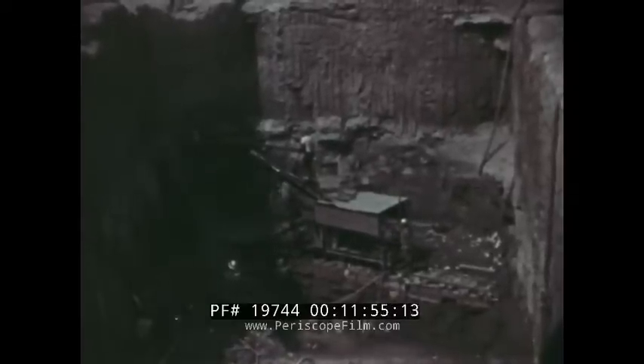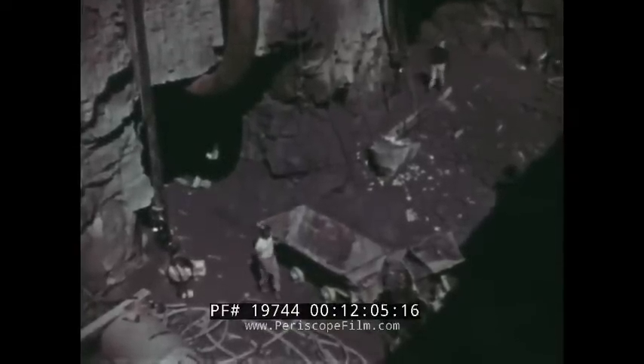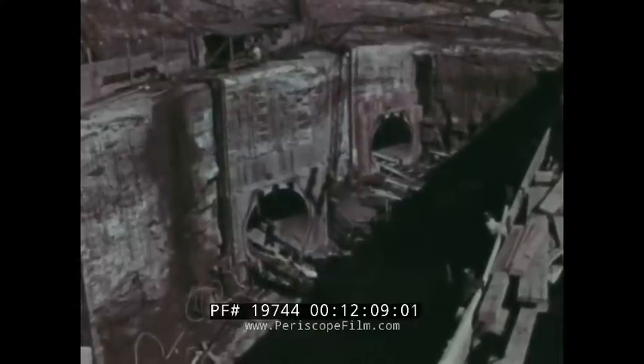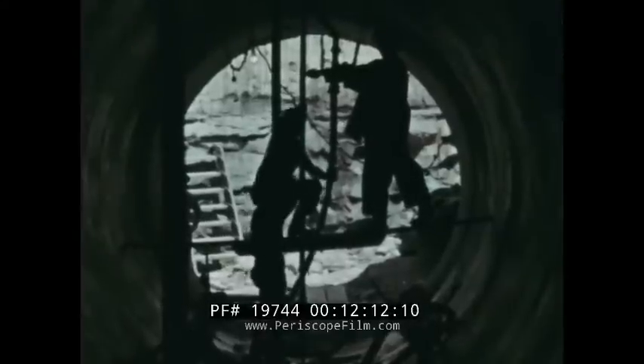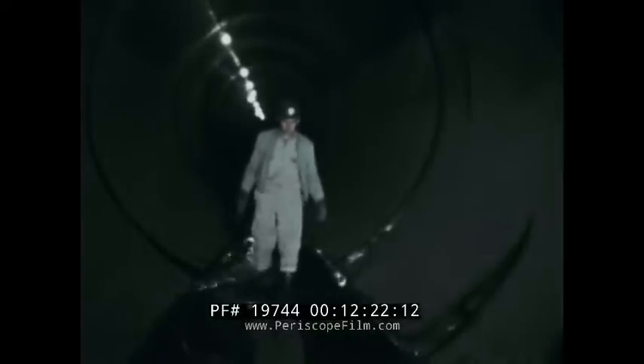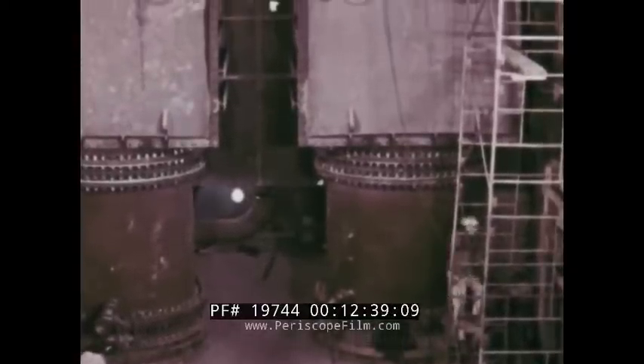To condense the steam used in the 2 turbo generators at Paradise requires almost 500,000 gallons of water a minute, nearly twice the needs of the city of Los Angeles. Tunnels with diameters of 11 feet, concrete lined, carry the water of the Green River to and from the condensers. Thousands of thin-walled brass tubes, extending through the condensers like holes in a thick sieve, carry the water for condensing the surrounding steam. Cooling the steam quickly reduces the pressure in the final stages of the turbines to a near vacuum. Thus, the colder the condensing water, the more efficient the turbo generator.